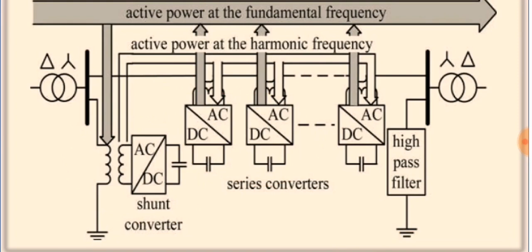The parallel converter takes the real power from the transmission line at the fundamental frequency while inserting the current back into the series converter at harmonic frequency. The transmission line carries harmonic current which is used in the series converters to produce the required aggregate of real power at fundamental frequency by generating the voltage at harmonic frequency. In this way, active power is exchanged between the series and shunt converters.